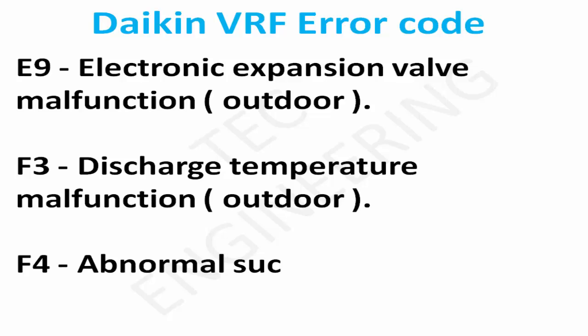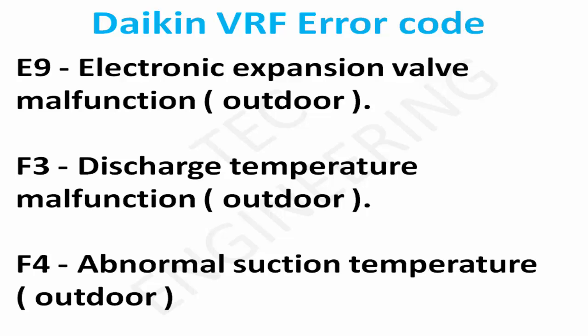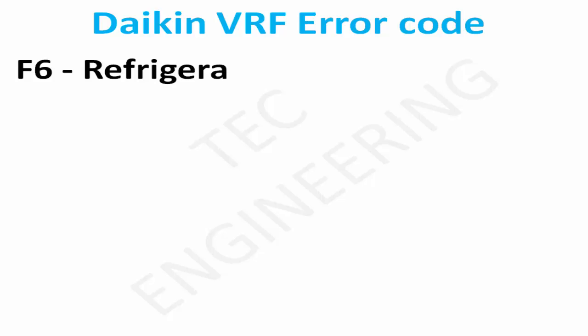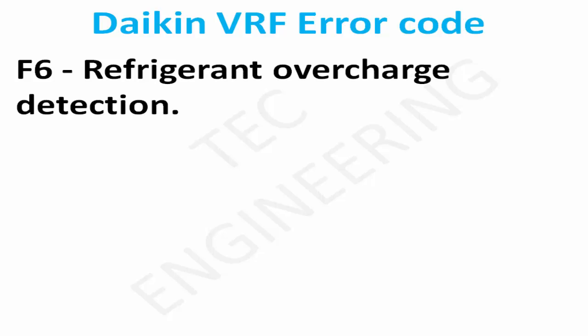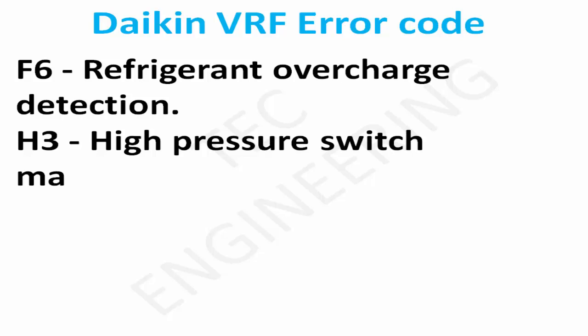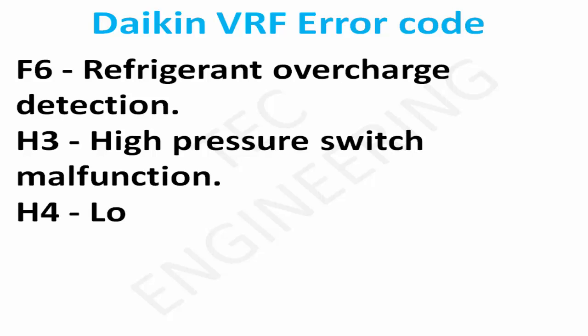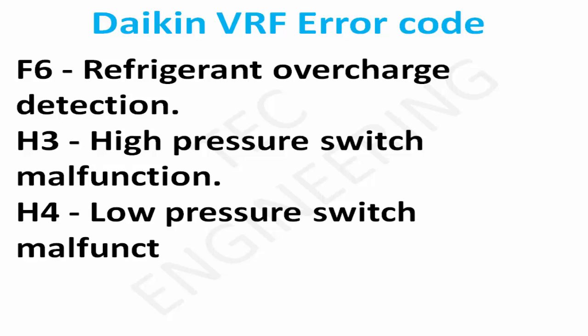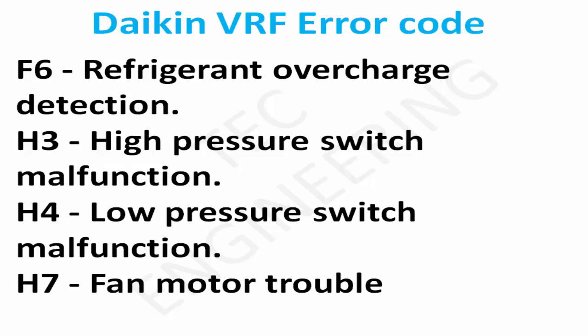F4: Abnormal suction temperature, outdoor. F6: Refrigerant overcharge detection. H3: High pressure switch malfunction. H4: Low pressure switch malfunction. H7: Fan motor trouble, outdoor.